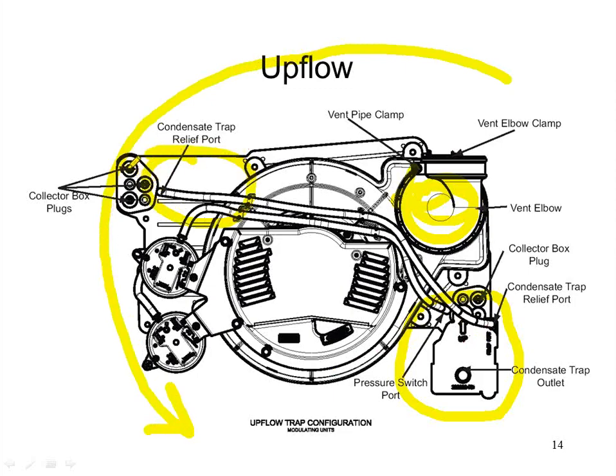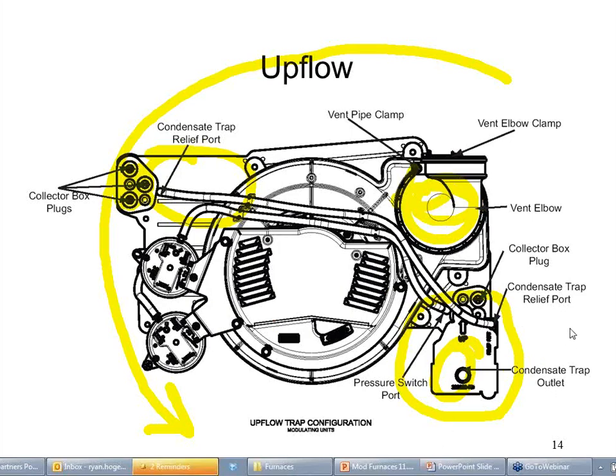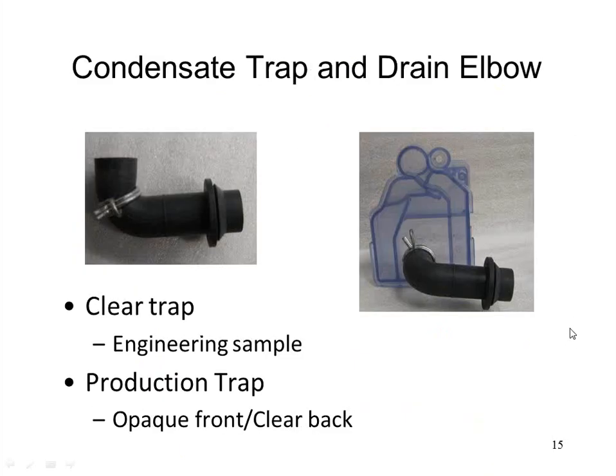So if you notice here, there's a couple little plugs on the left side over here, collector box plugs. I take those out. I move this condensate trap over there. I put the plugs on the other side. Life's good. I'm ready to go. So if I want to rotate this guy, all I got to do is rotate the venting elbow and flip-flop the condensate trap, and I can move this guy into different orientations. Those are the only two things I really have to move around.